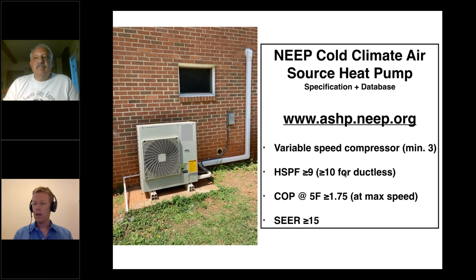What's really important here is that it's a great place to go for details on the cold weather performance for these heat pumps. All of the manufacturers who publish information in this database are required to publish the maximum heat output at 5 degrees outdoor temperature, which is really close to a lot of your design temperatures, which is great. As you start getting into the details on heat pumps and various models and their heating output, you're really going to want to dig into the details in the expanded engineering tables or engineering design manuals.